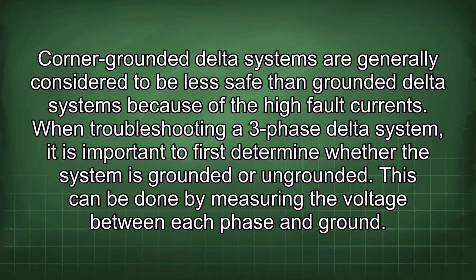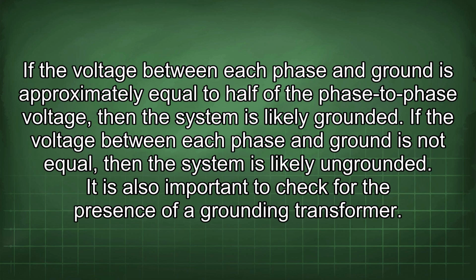the high fault currents. When troubleshooting a three-phase delta system, it is important to first determine whether the system is grounded or ungrounded. This can be done by measuring the voltage between each phase and ground. If the voltage between each phase and ground is approximately equal to half of the phase-to-phase voltage, then the system is likely grounded. If the voltage between each phase and ground is not equal, then the system is likely ungrounded.